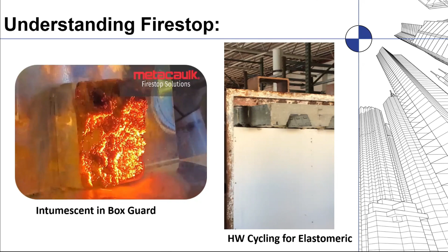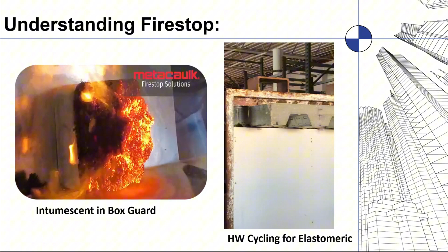When it fills like this, it keeps the fire, heat, and smoke from making its way through the electrical box to the other side of the structure, where the electrical plugs would be. Once the flame is removed, it's self-extinguishing. That's the char I'm talking about—it creates a shell and nothing else gets through it.